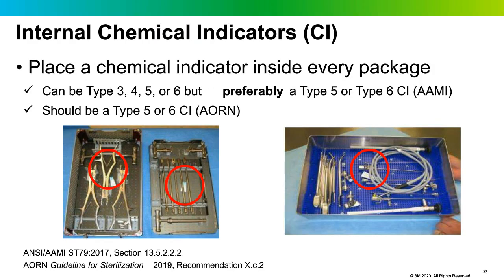OR staff check the internal chemical indicator placed inside every package. ST-79 now recommends the preferred use of a Type 5 or Type 6 indicator. Type 6 emulating indicators are labeled for specific cycles, while Type 5 integrating indicators typically have broader indications and most facilities find them the most practical choice. AORN states that the internal chemical indicator should be read and interpreted before the tray or item is placed on the sterile field. If a pass result hasn't been achieved, you reject the tray.